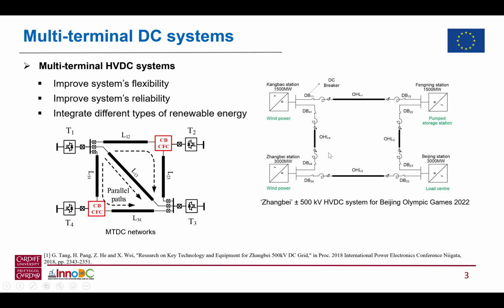Nowadays, most of the HVDC systems are still point-to-point links, but in the future, there's a trend, a possibility that we can connect the existing point-to-point links to form multi-terminal or meshed MTDC networks in order to improve the system's flexibility and reliability. And in such systems, we can integrate many different kinds of renewable energies into the multi-terminal HVDC systems. There's also an example which is constructed in China. It is a four-terminal meshed HVDC system, and the voltage rating is 500 kilovolts.